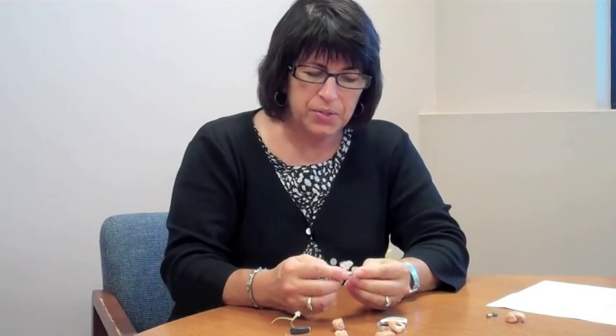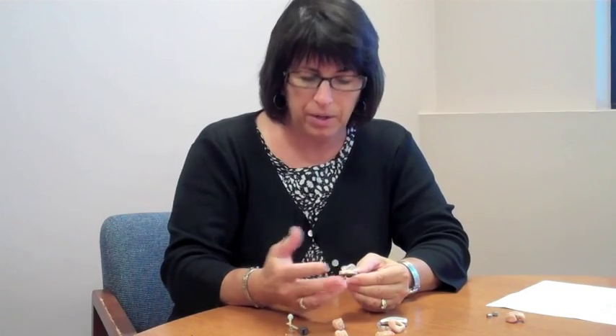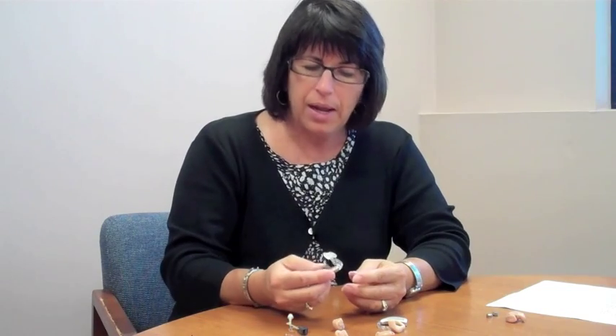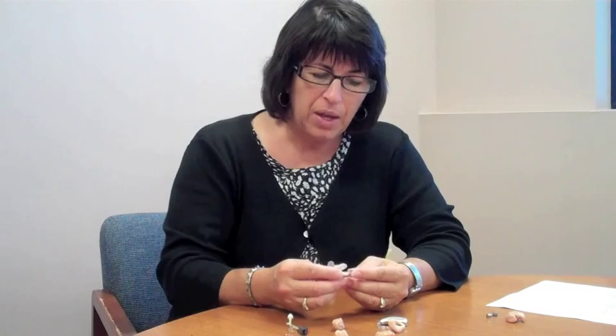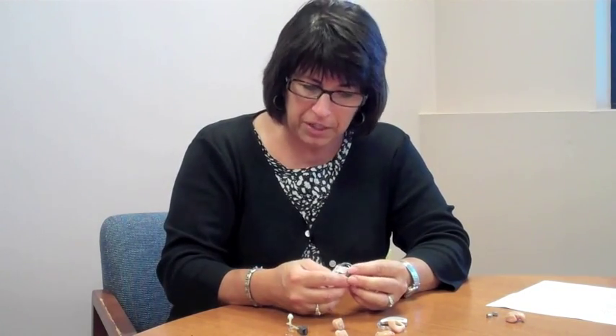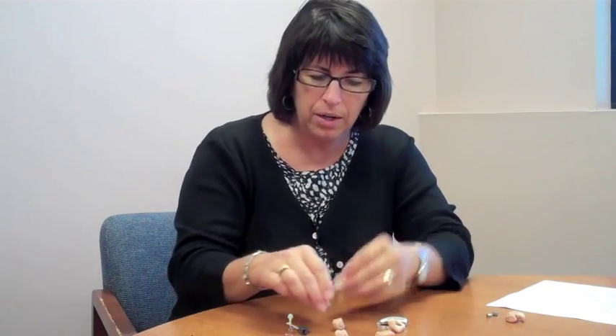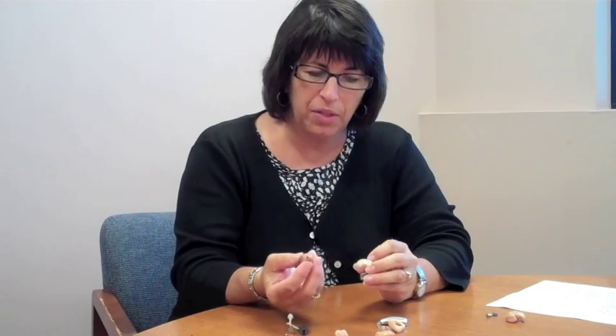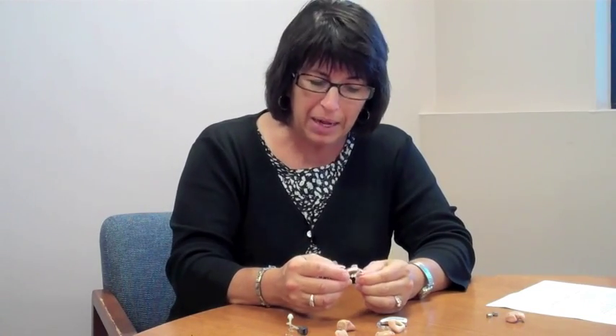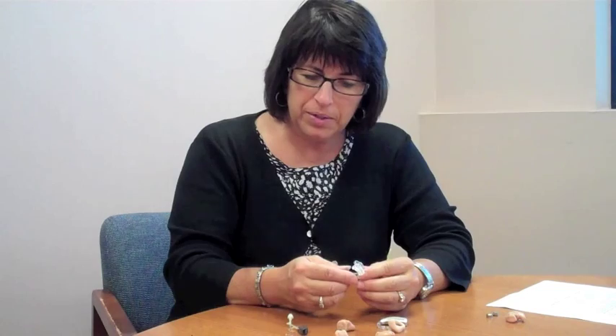Another topic we'll address is if a hearing aid is whistling or has feedback, another word for that whistling sound. It can be due to probably three main things. First thing we want to check is if the user or patient has a wax problem. So using an otoscope, we'll look in their ear to see if wax might be causing the problem. Secondly, it could be that the hearing aid is not fitting tightly, and it can be the mold on a behind-the-ear hearing aid, or the hearing aid itself in an in-the-ear style. The third thing is there could be actually something wrong with the hearing aid. Internal feedback, which is a problem in the hearing aid, can also cause a hearing aid to whistle. So it's a matter of process of elimination to figure out why the hearing aid is whistling.